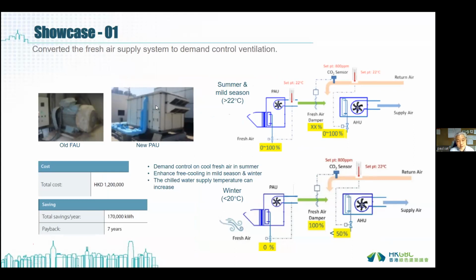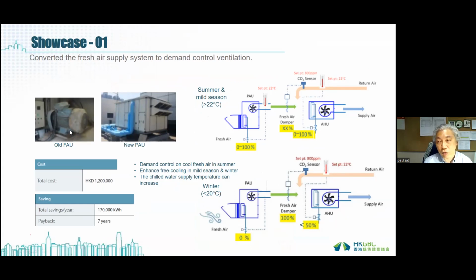The first showcase is a building where they replaced the existing, very old fresh air fan with primary air units. And they integrated demand control together with the primary air units. The benefit is that in conventional control, they would bring so much fresh air into the building and also increase the cooling load. But when you use the primary air unit, with pre-treated cooling for the fresh air together with CO2 demand control, they can minimize the amount of fresh air, and also you can do free cooling in winter or mild seasons, and also reduce the cooling load demand in summer for occupants.